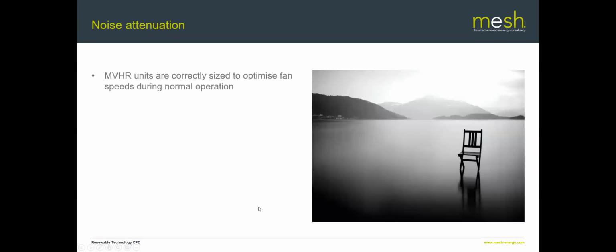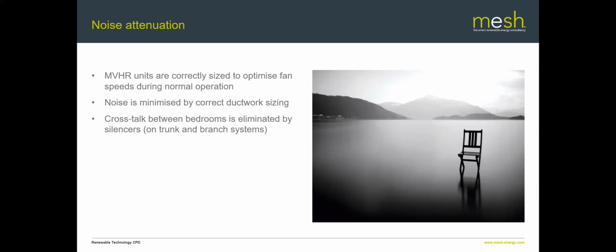So what do we do about noise? Well, as I say, we correctly optimize the fan speed and the design of that. We make sure the ductwork sizing is correct. So that means really reducing the velocity in the branch ducts down to about 2 meters per second, and in the trunk ducts down to around 3 meters a second, and that tends to be enough to minimize noise from the ductwork.